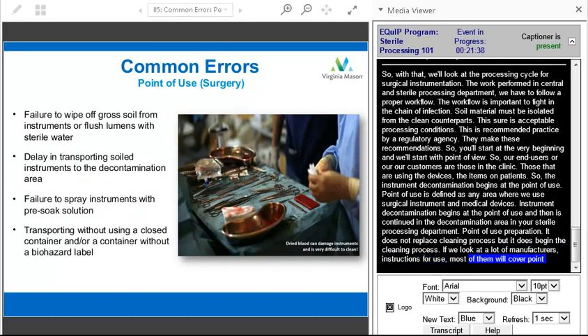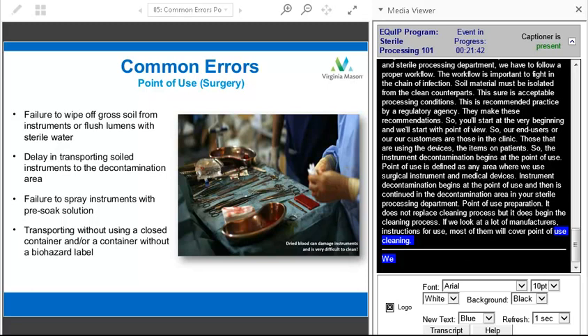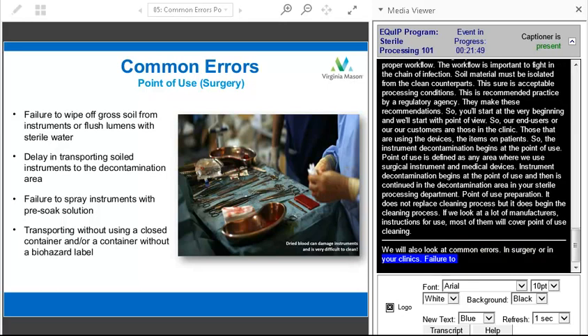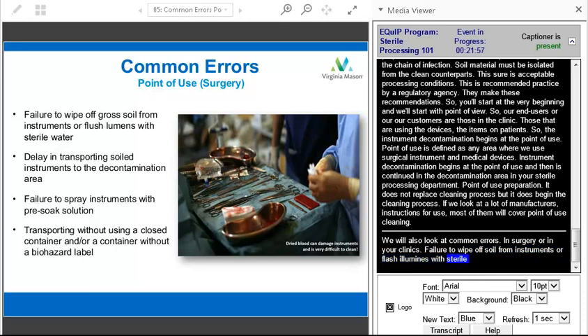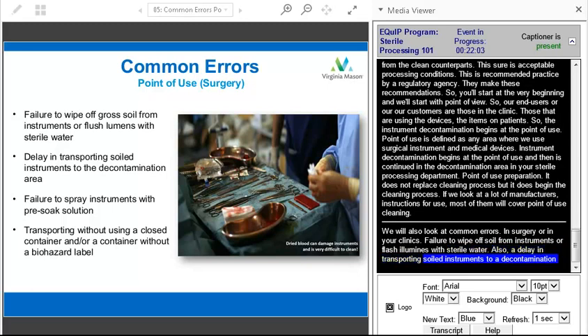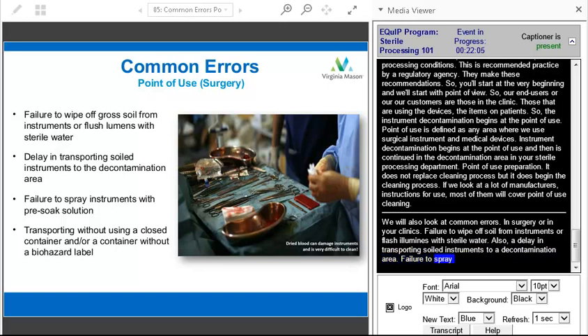So we'll also look at common errors from point of use in surgery or in your clinics. Failure to wipe off gross soil from instruments or to flush lumens or suctions with sterile water during the procedure. Also a delay in transporting soiled instruments to the decontamination area. Failure to spray instruments with a pre-soaked solution. Some have enzymatic sprays and that.